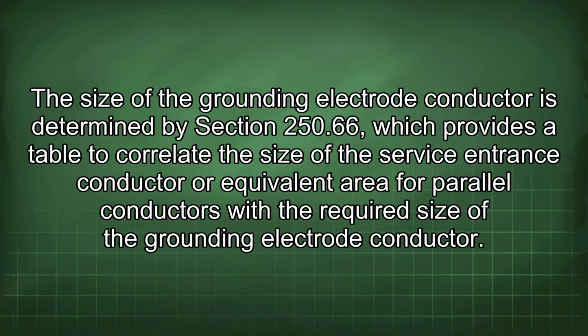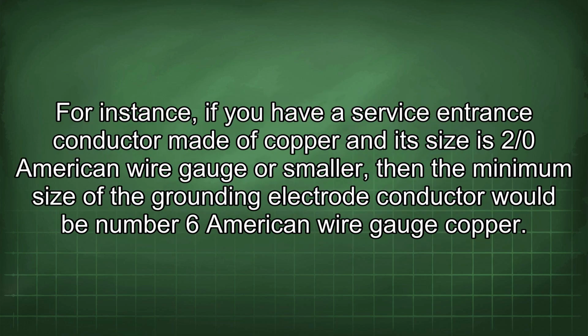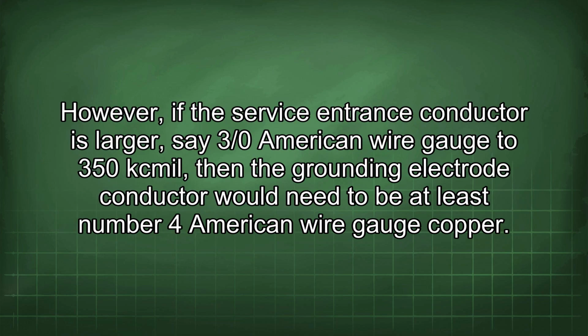The size of the grounding electrode conductor is determined by Section 250.66, which provides a table to correlate the size of the service entrance conductor or equivalent area for parallel conductors with the required size of the grounding electrode conductor. For instance, if you have a service entrance conductor made of copper and its size is 2/0 American wire gauge or smaller, then the minimum size of the grounding electrode conductor would be number 6 American wire gauge copper. However, if the service entrance conductor is larger, say 3/0 American wire gauge to 350 kcmil, then the grounding electrode conductor would need to be at least number 4 American wire gauge copper.